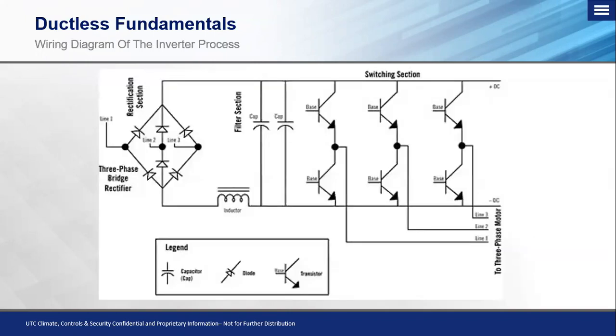So if we look at this from a schematic point of view, you'll see here you have your main power coming in. Now, in this case, of course, we only have single phase equipment in the ductless product line, so we can just knock off this phase right here for line 3. We have our incoming power, as you can see right here, which is entering into this little diamond looking shape. This is the bridge rectifier, and you can see here by the electrical layout you have your diode stacks. And this is where we talked about before, where that AC to DC conversion happens.